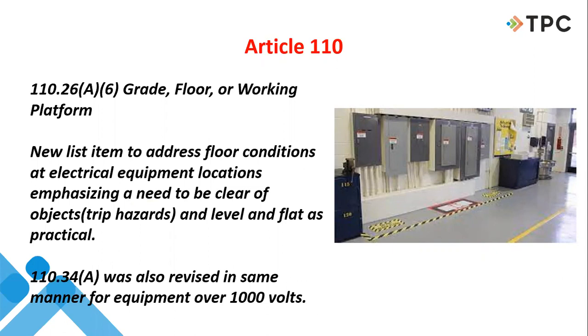Especially when you're walking around, you have panels and covers open, there are energized components exposed, and you're already investing your attention in making sure nothing goes wrong in that department. Now you have to make sure you don't trip over anything on the floor as well. They're trying to do away with one of the things that might distract us or might cause an accident. 110.34(A) is the same thing, but for equipment over 1,000 volts.